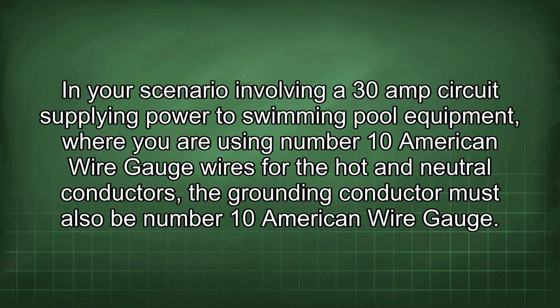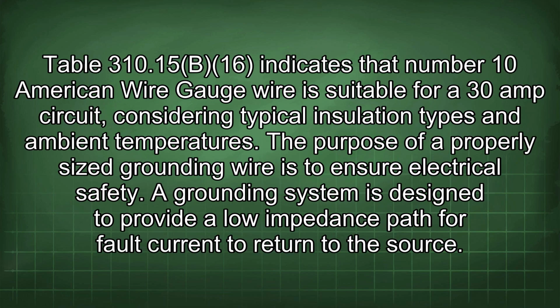circuit. In your scenario involving a 30 amp circuit supplying power to swimming pool equipment, where you are using number 10 American wire gauge wires for the hot and neutral conductors, the grounding conductor must also be number 10 American wire gauge. Table 310.15(B)(16) indicates that number 10 American wire gauge wire is suitable for a 30 amp circuit, considering typical insulation types and ambient temperatures. The purpose of a properly sized grounding wire is to ensure electrical safety.